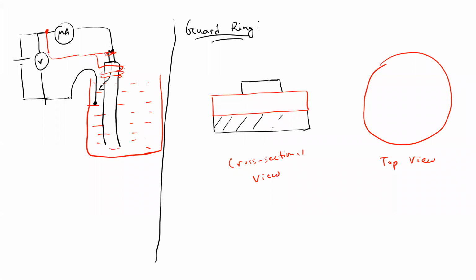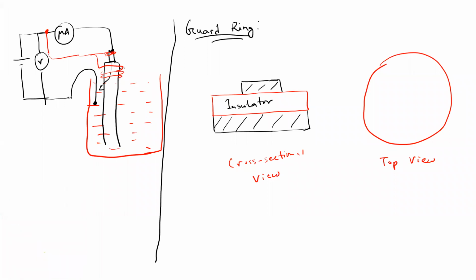So suppose this is the upper conductor, this is the lower conductor, and on the top surface, another contact will be placed, which can be referred to as the guard ring. The purpose of the guard ring is to bypass the leakage current flowing through the surface.